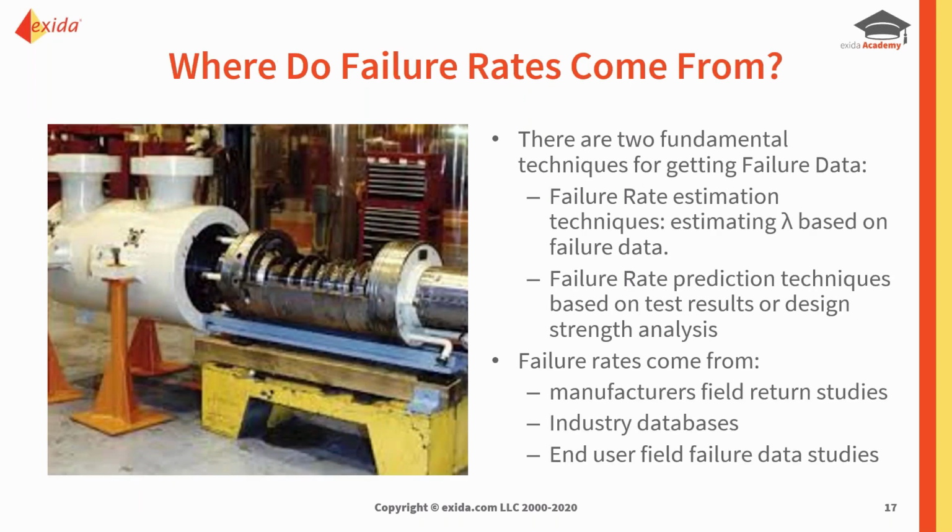So where do they come from then? Well, from that, we should be able to estimate our failure rates based upon this failure data. So obviously, if the failure rate data isn't very accurate and isn't reliable, then our estimation of our failure rate itself is going to be questionable. The other way is to do a failure rate prediction using prediction techniques such as FMEDA as one approach, or you can do it as a mix of based on design strength analysis and test results.